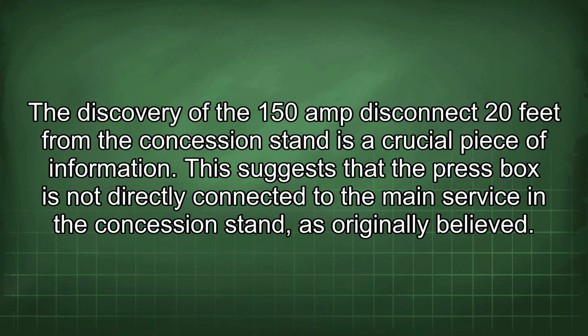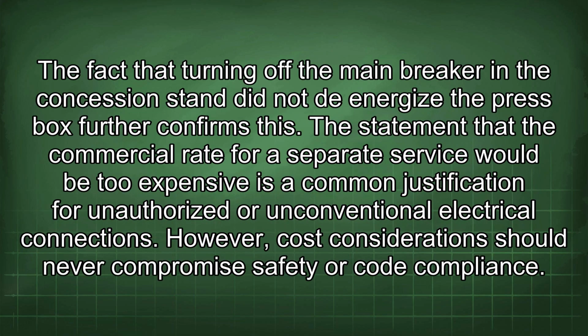The discovery of the 150 amp disconnect 20 feet from the concession stand is a crucial piece of information. This suggests that the press box is not directly connected to the main service in the concession stand, as originally believed. The fact that turning off the main breaker in the concession stand did not de-energize the press box further confirms this. The statement that the commercial rate for a separate service would be too expensive is a common justification for unauthorized or unconventional electrical connections. However, cost considerations should never compromise safety or code compliance.